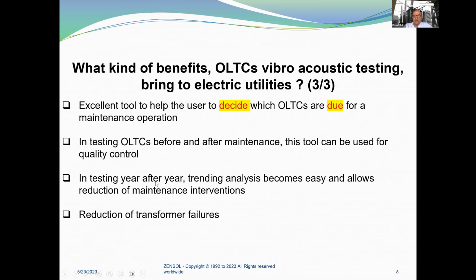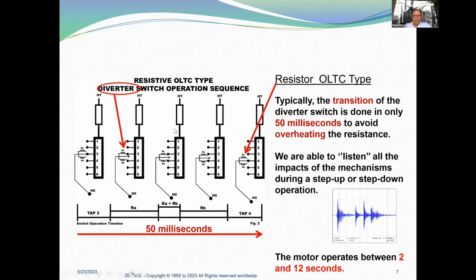And in testing year after year, trending analysis becomes easy and allows a reduction of maintenance interventions. And of course, our goal is to reduce transformer failures. Here you have a resistive OLTC type diverter switch operation sequence. For example, here we are in tap 3, and we are moving to tap 4.